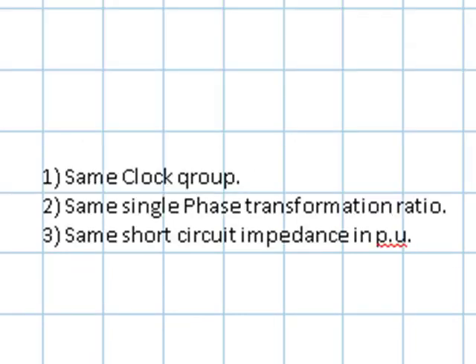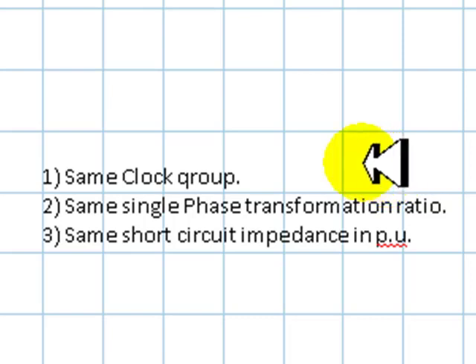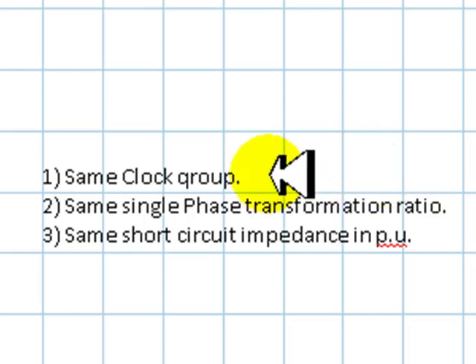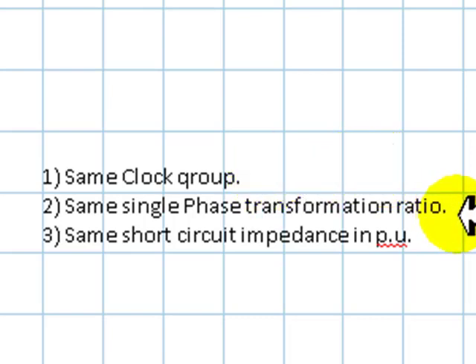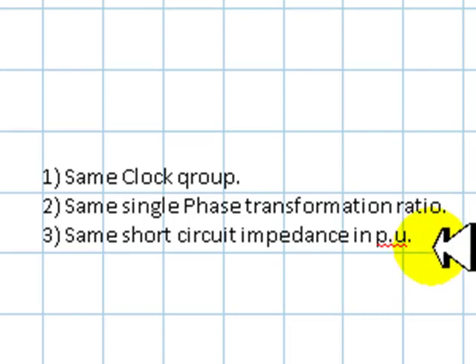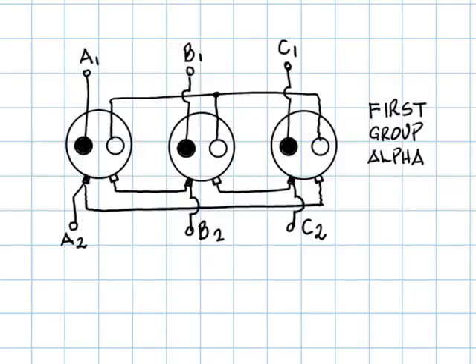To connect them in parallel, we should check that they are of the same clock group, that they have the same single-phase transformation ratio, and that they have the same per-unit short-circuit impedance. Let's begin with the clock group for the first group, Group Alpha.